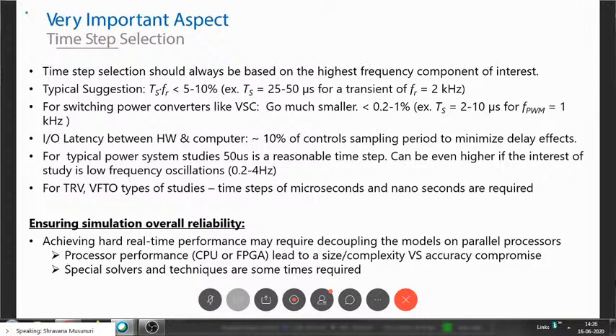In the same power systems application, there's also something called VFTO, very fast transient overvoltages. This is a study typically applied for GIS substations. VFTO deals with the fast transient overvoltages that appear across the bushings within a substation. They are of the order of megahertz. So to effectively capture that, you would need to go to the nanosecond level. Based on my experience, it is better to go to 1 nanosecond or maybe smaller, like 0.5 nanoseconds.